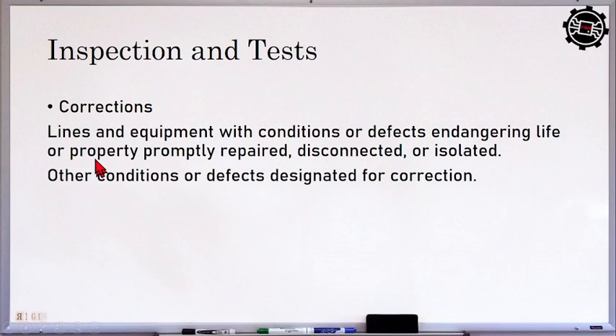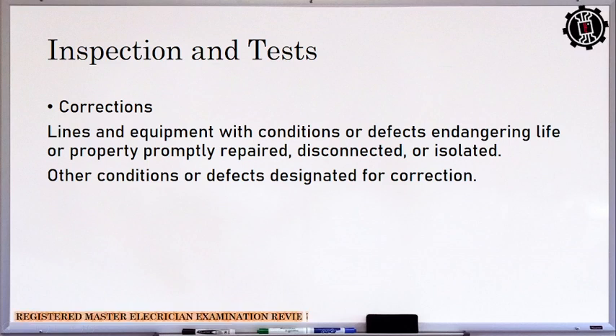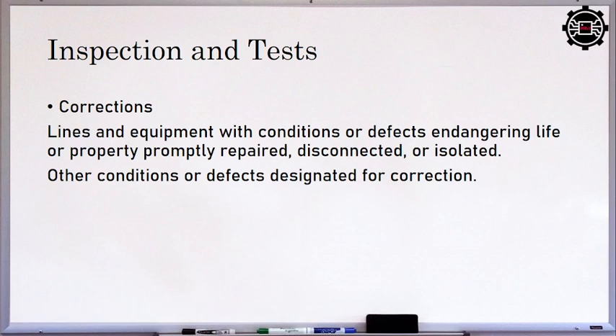Then corrections, so lines and equipment with conditions or defects endangering life are promptly repaired, disconnected or isolated. So dapat if that defect or that condition can endanger life either doon sa mga gagamit or doon sa magmi-maintain or the mga qualified persons, so it must be repaired immediately. If hindi siya agad ma-repair, then it must be disconnected to the system tapos i-isolate. Then other conditions or defects designated for correction. So if a certain defect hindi naman siya pwedeng maka-endanger sa life, i-record lang siya until there will now be the schedule for preventive maintenance to correct that minor defects or abnormality.